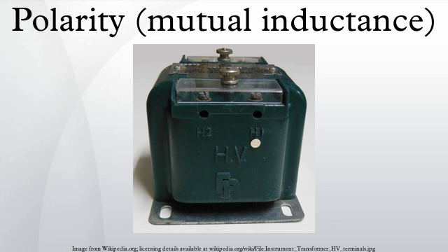Transformer windings: two methods are commonly used to denote which terminals present the same relative polarity. A dot may be used, or an alphanumeric designation. Alphanumeric designations are typically in the form H1 for primaries, and for secondaries, X1. Unlike single-phase transformers, three-phase transformers may incorporate a phase shift due to different winding configurations, resulting in a multiple of 30-degree phase shift between H1 and X1 bushing designations.